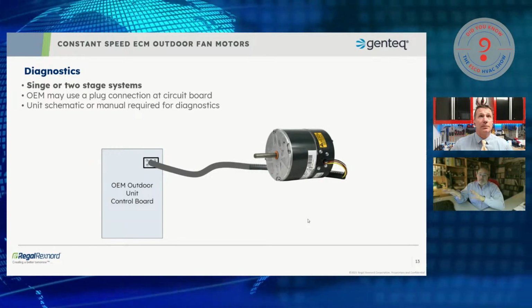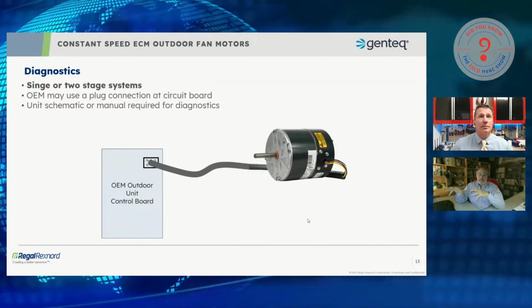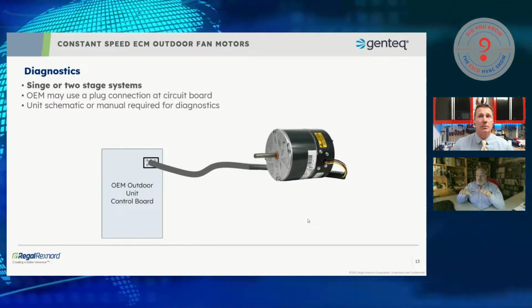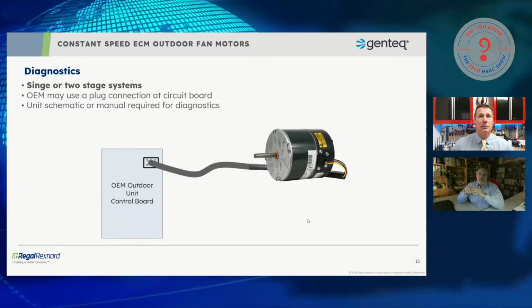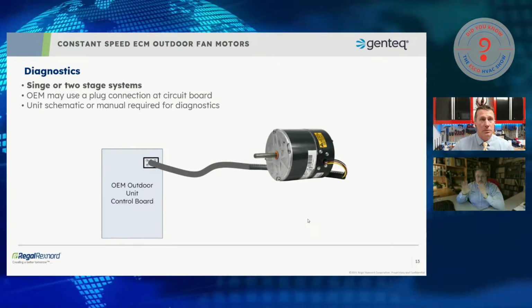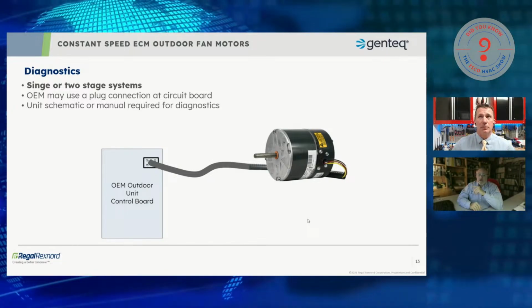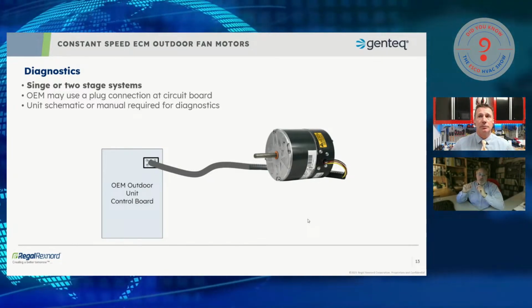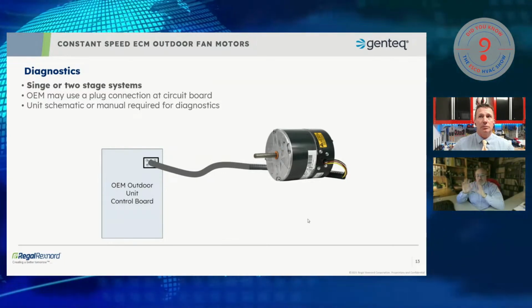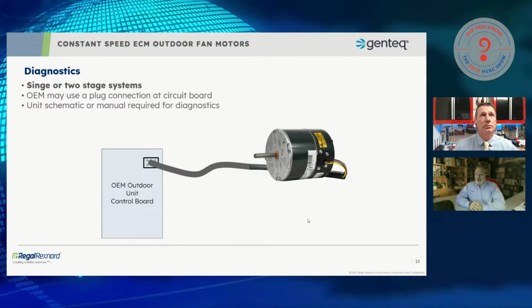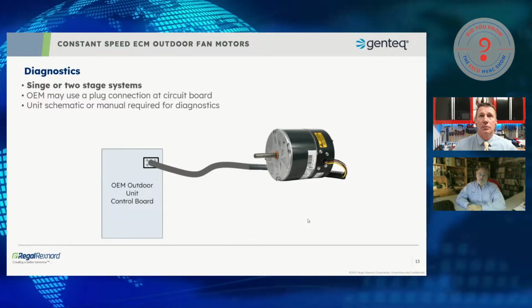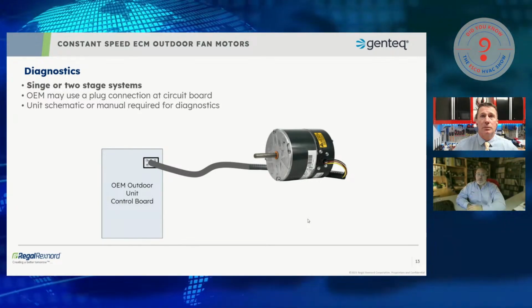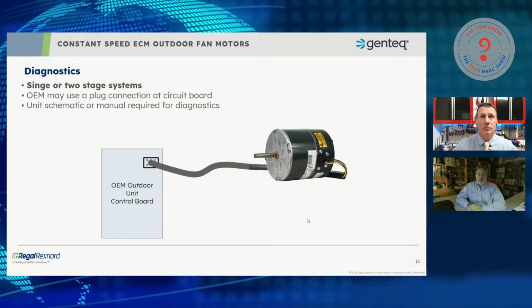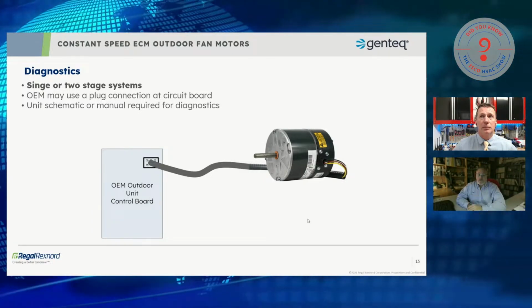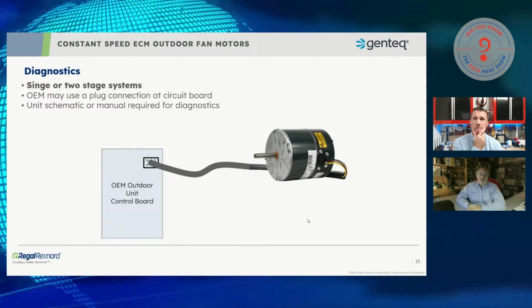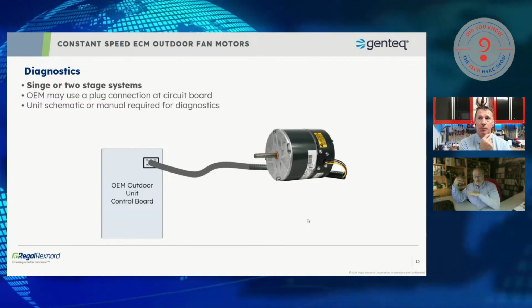Now, most of my images so far have shown a circuit board where the motor goes back to the circuit board. There will be some systems where the motor connects to the board through a plug. If it goes through a plug, obviously we're going to have to get into the unit schematic on the door, hopefully it's still there and legible, or I may have to go back to the manual to find out which wire color goes to what. Versus if they're individually wired, usually the terminal on the board is labeled Y1, Y2. It's pretty easy to find out what those wires are. Also, there are some systems where there may or may not be a circuit board, and the motor might literally be wired directly to the contactor. The line voltage directly to the load, or even the line side of the contactor, and the low voltage, if it's 24-volt discrete speeds, literally connected directly to the thermostat wires that are coming into the outdoor unit from the indoor unit. So I wanted to cover that.